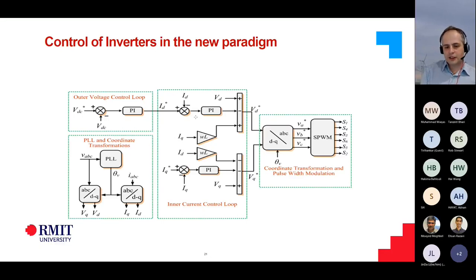We have some significant issues because of the quality of the voltage source which these networks, these inverters, are connected to. Majority of the inverters are designed by assuming we have a perfect voltage source, and we can use that perfect voltage source to provide the reference signal for our controllers, for I and V controllers. And all of these rely on a very important element, which is the PLL. So the PLL provides the reference points for these controllers inside the inverters.